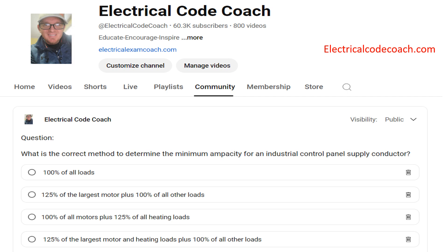What is the correct method to determine the minimum ampacity for an industrial control panel supply conductor? The correct answer is 125% of the largest motor and heating loads plus 100% of all other loads.